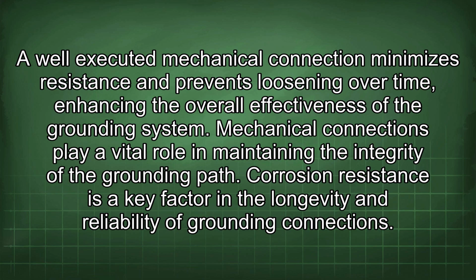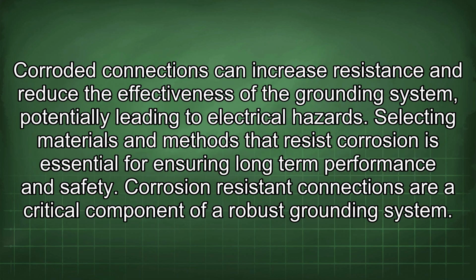Corrosion resistance is a key factor in the longevity and reliability of grounding connections. Corroded connections can increase resistance and reduce the effectiveness of the grounding system, potentially leading to electrical hazards. Selecting materials and methods that resist corrosion is essential for ensuring long-term performance and safety. Corrosion-resistant connections are a critical component of a robust grounding system.